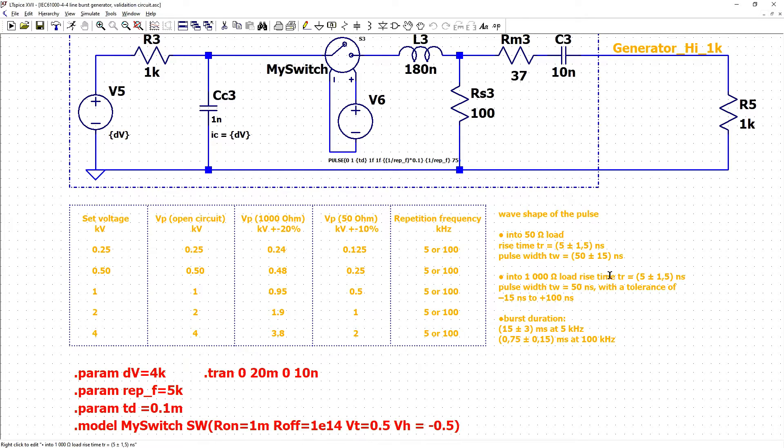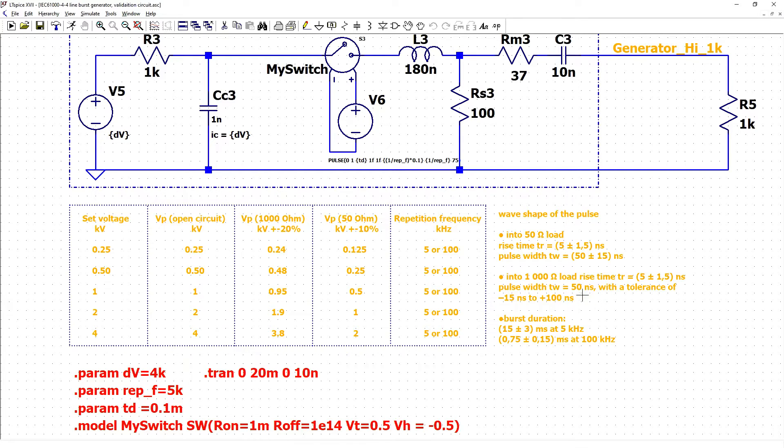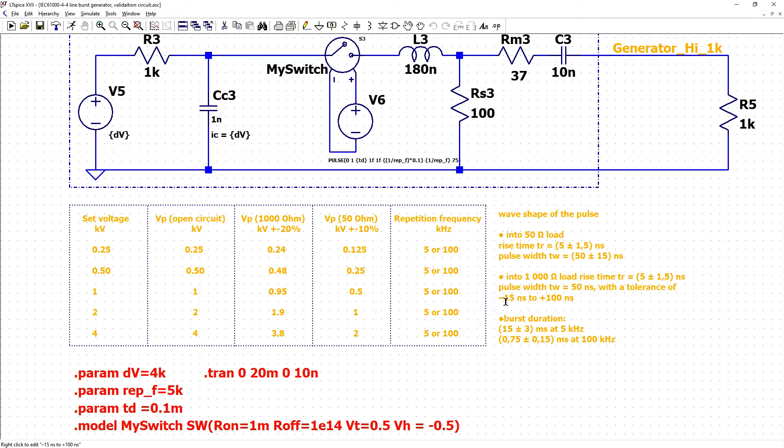Rise time should be the same 5 plus minus 1.5 nanoseconds and pulse width could be different because we have 50 ns but the tolerance is higher from minus 15 ns to plus 100 ns. The maximum value here could be 150 ns.